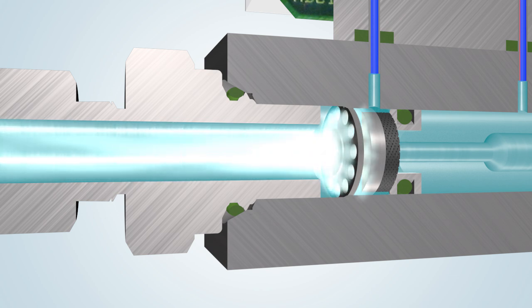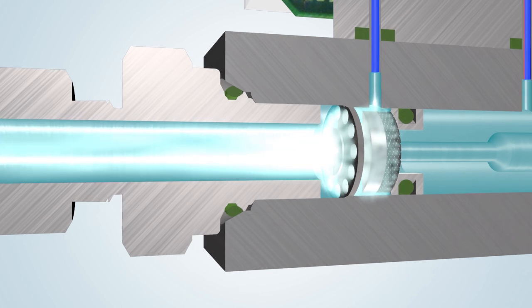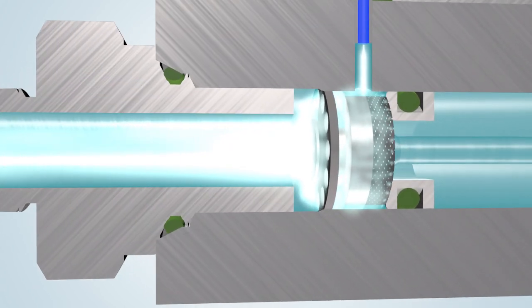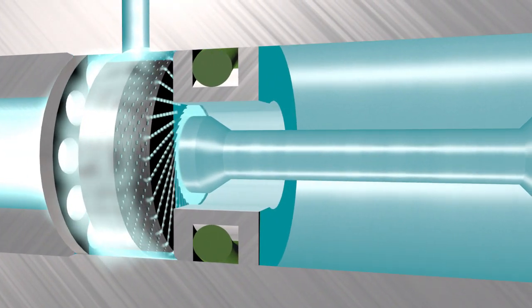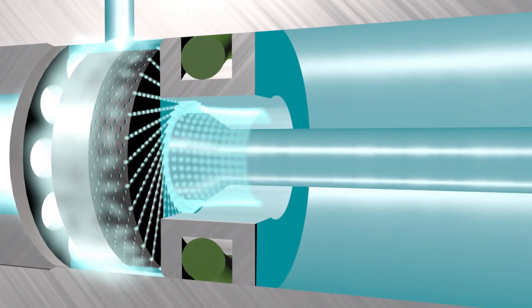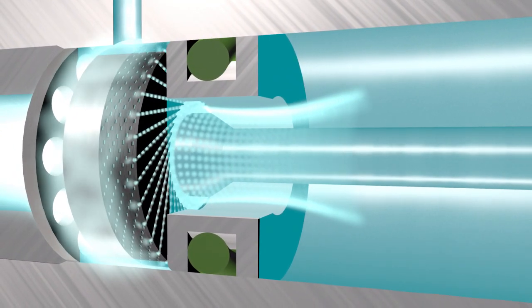The gas flows through the laminar flow element, which serves as a perfectly predictable flow resistance. This makes it possible to build and calibrate an instrument for use on nitrogen and to model it for any other gas.